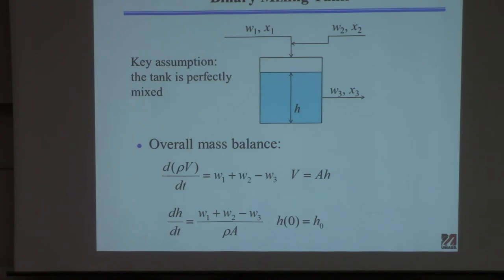So, you know, you could write this equation either for the volume of fluid in the tank. People usually do it for the level because if you're in a plant, you usually actually measure the level. You don't measure the volume, so people tend to write the models in terms of level instead of volume. But obviously, they only differ by A, the cross-sectional area. So there you go. So to do this, to solve this equation, right, in addition to knowing these flows, I would need to know the initial level. Okay? So there's the overall mass balance.